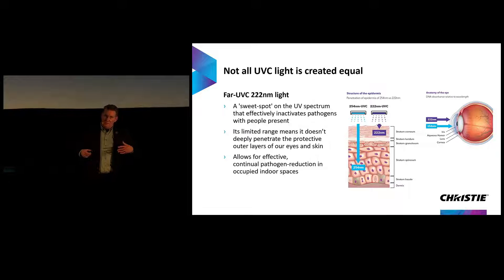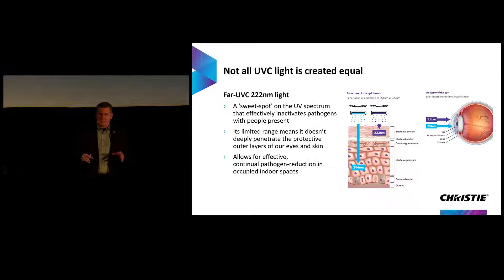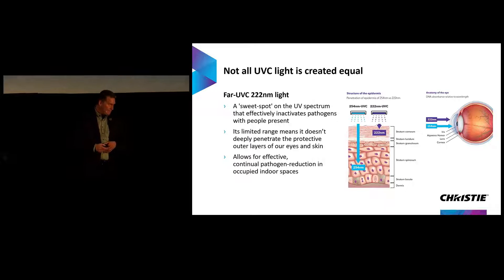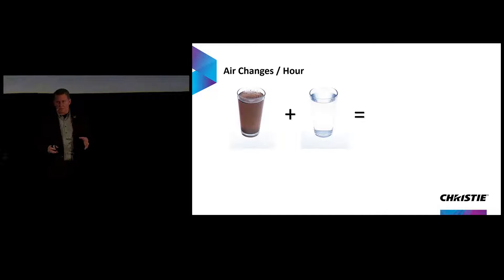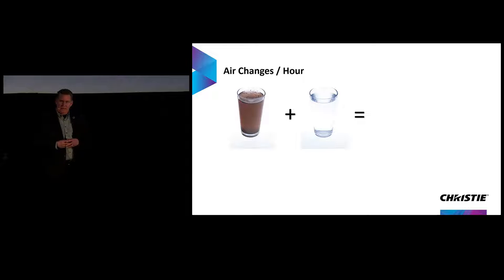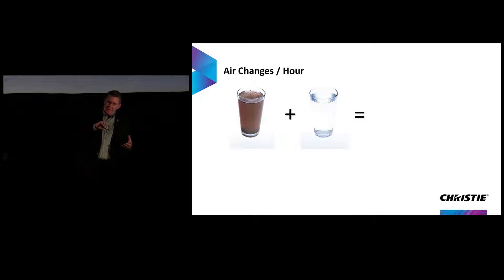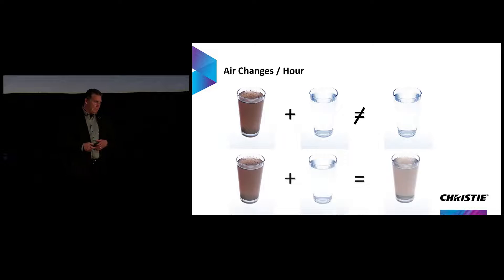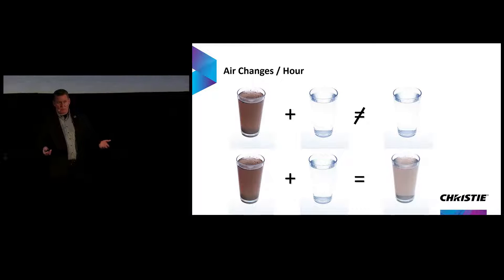This is fantastic — it enables UV light to be used in occupied spaces. No longer are we just disinfecting empty spaces; now we can be actively disinfecting spaces while people are there. So let's talk about air changes per hour. If we think of the dirty glass as our pathogen-laden room and the clean glass as one air change, when we take the clean water and dump it into the glass of dirty water, we don't end up with clean water — we end up with something less dirty. The same is true with a pathogen-laden space: when you add one air change, you typically see a concentration reduction of about 65%.